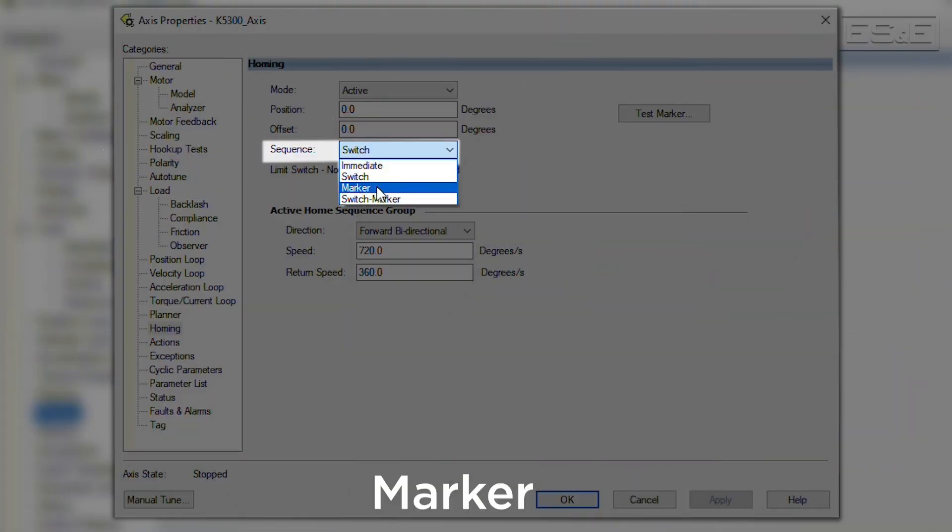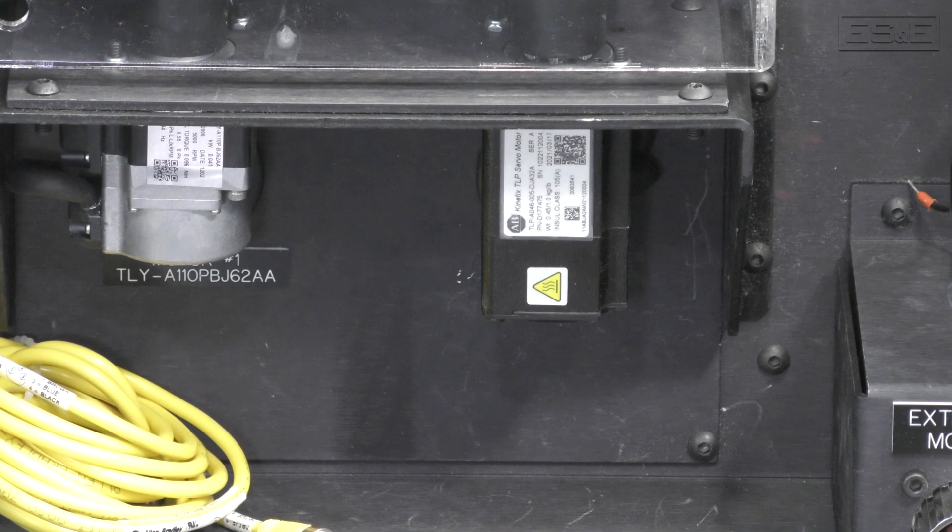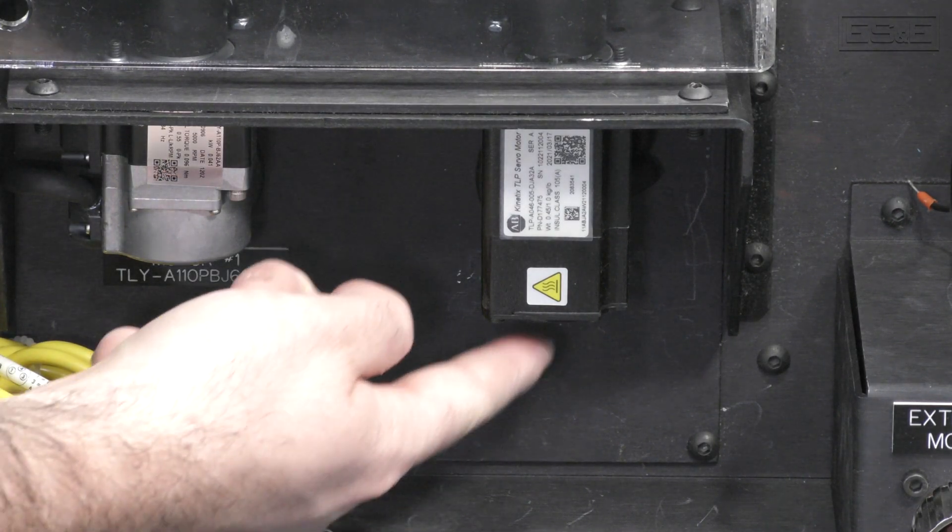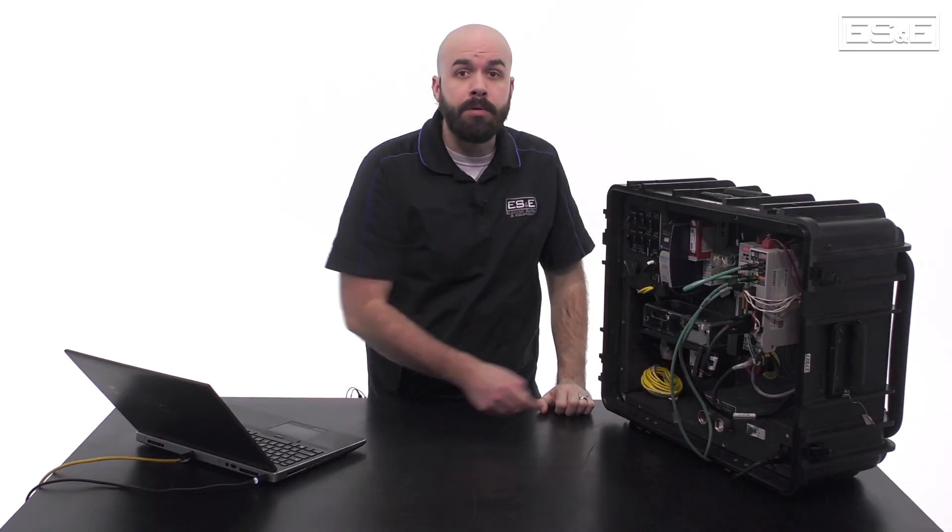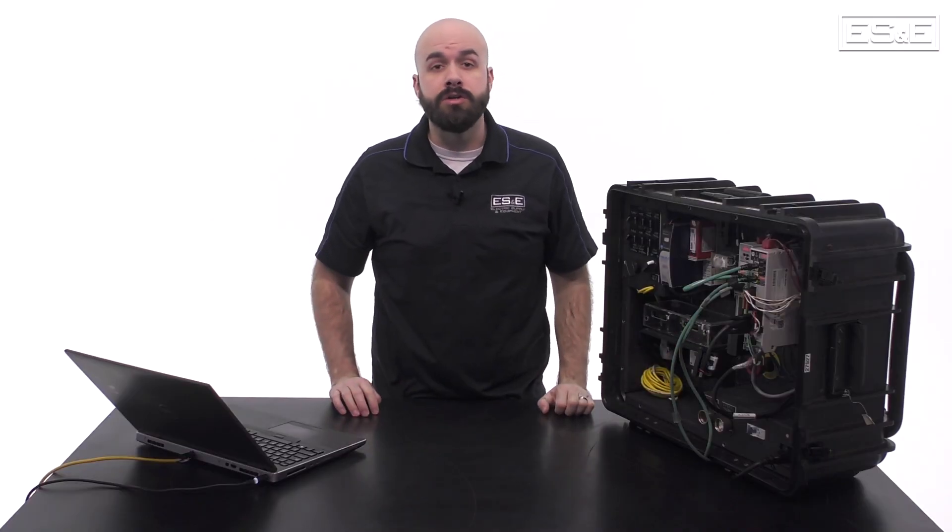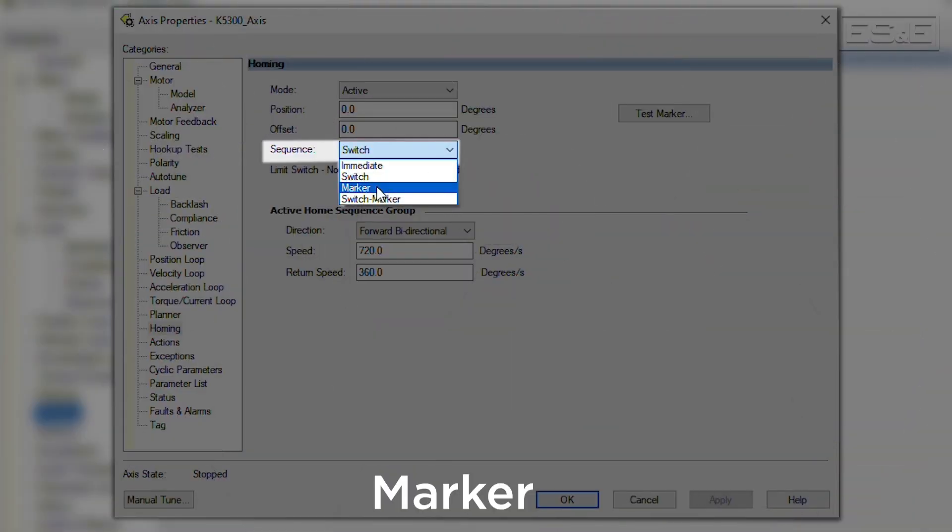If marker is selected, then the axis will need to move to the marker pulse that is built into the encoder on the back of the servo motor. The marker pulse occurs once every revolution of the encoder. Again, when the mode is active, the servo will automatically move until the marker pulse is detected. Once the marker pulse is detected, the actual position will be redefined at that point.